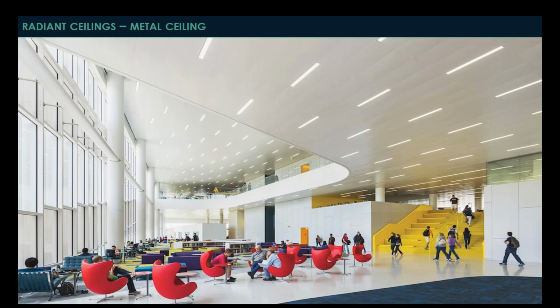So another type of radiant ceiling is the overall metal ceiling. There are companies out there, Armstrong comes to mind because they've been very big in the metal ceiling industry for a very long time. And these types of metal ceiling systems really lend themselves well to radiant because you already have the metal surface available to you. It's really just activating a portion of that surface in a similar way to the modular and the linear panels, where you simply run copper tubing and you're attaching that directly to a portion of the metal ceiling system.